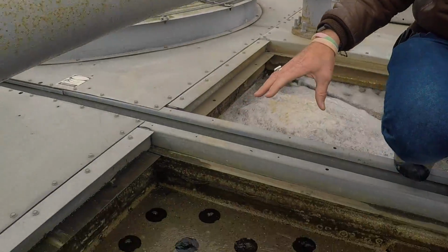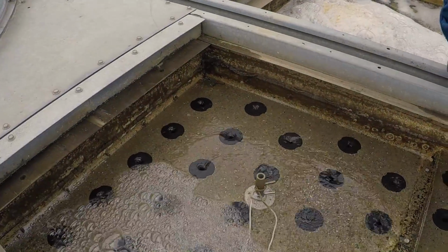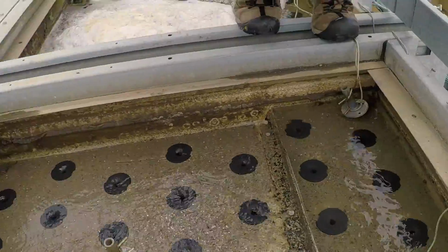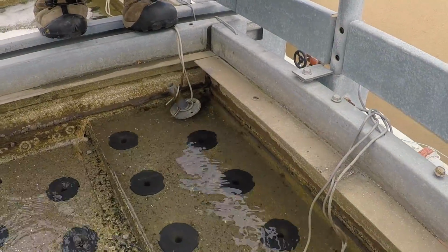Okay. The second thing is, if you get the nozzle curves, and the nozzle curves are something I always try to get on new construction because they're harder to get after the fact, but if you get the nozzle curves, then if you know the depth over the nozzles and the number of nozzles, you know how many gallons per minute.